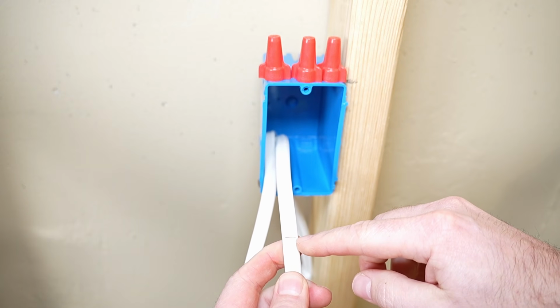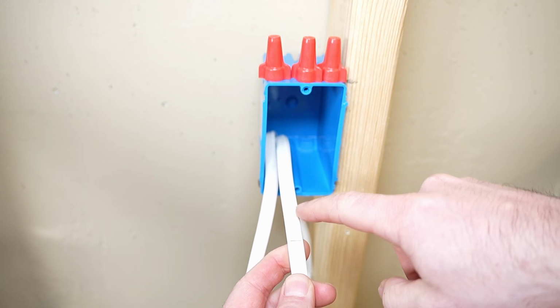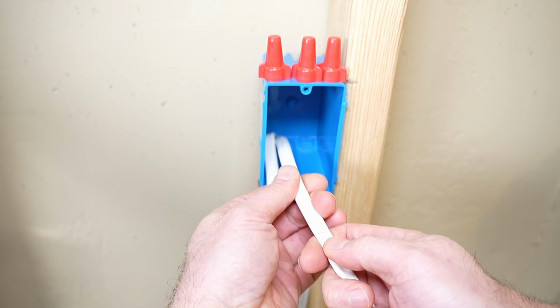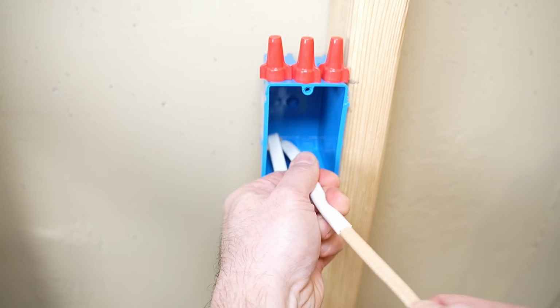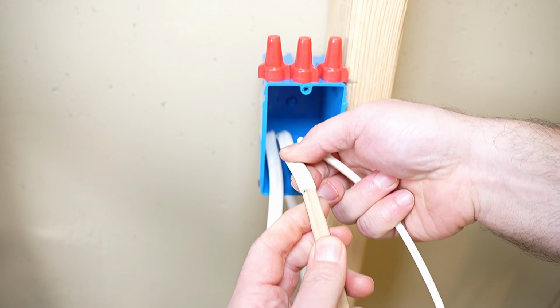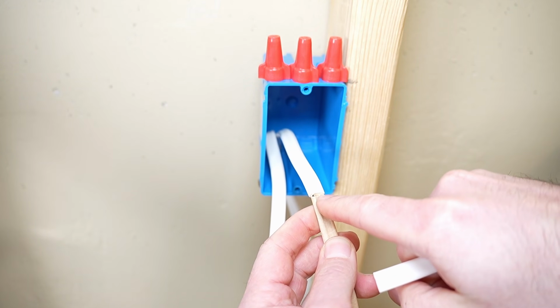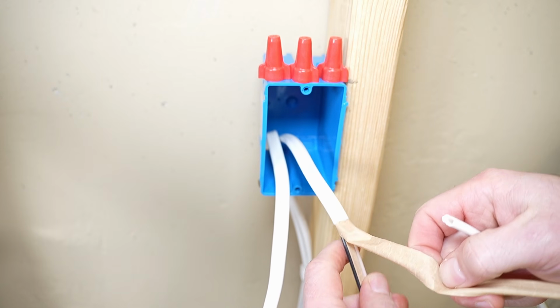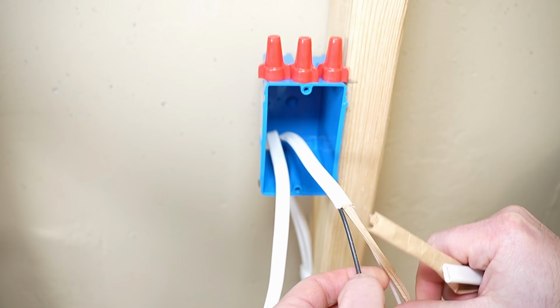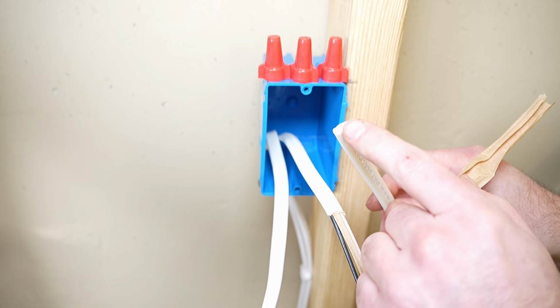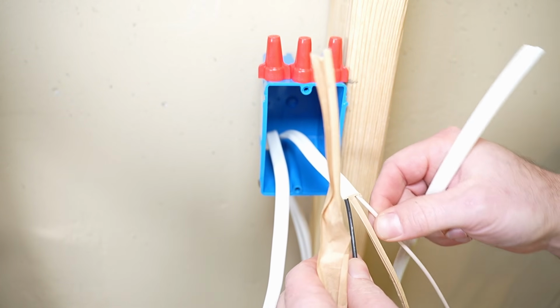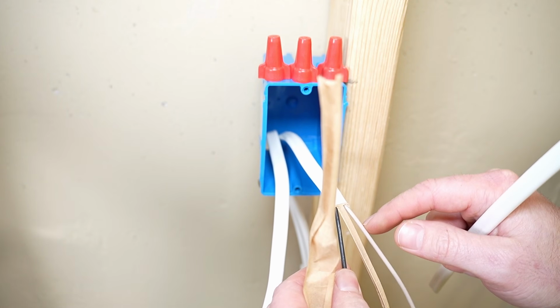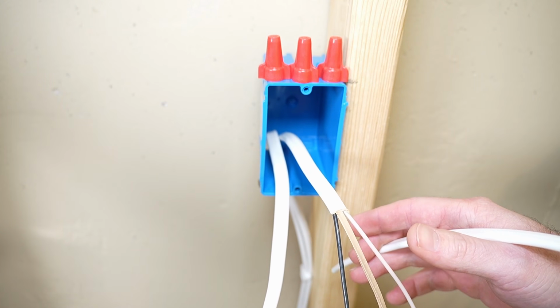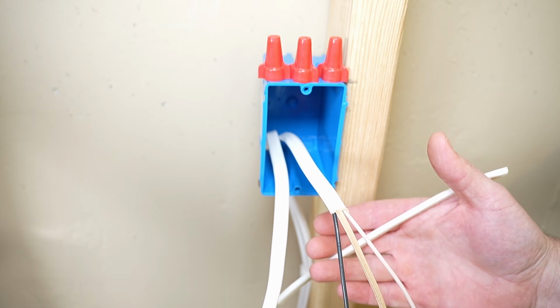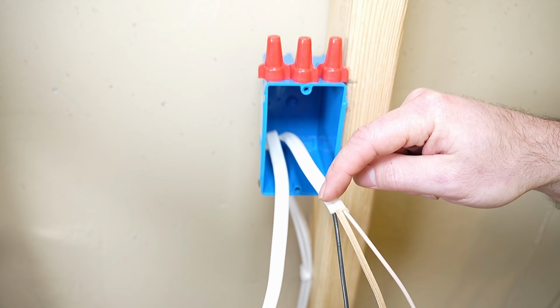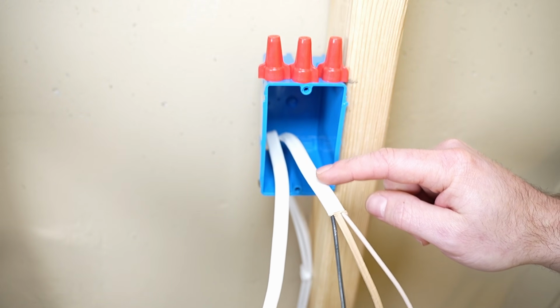I just scored through just enough that the outer insulation is starting to split. And then we can give it a pull and actually tear it the rest of the way. But check it out. I did not actually cut through enough to even cut through the paper completely. So the point is we're just scoring this outer sheath. We do not want to be cutting the insulation on these inner wires. And for a beginner, that can be very difficult. I used to struggle with that a lot. You are only using light pressure to score through the insulation here.